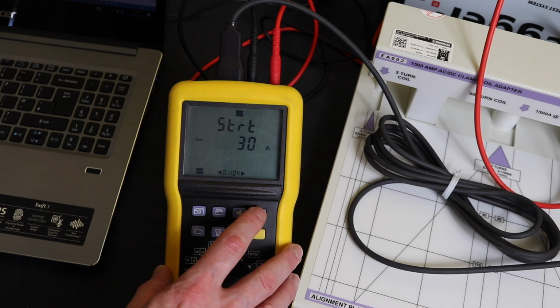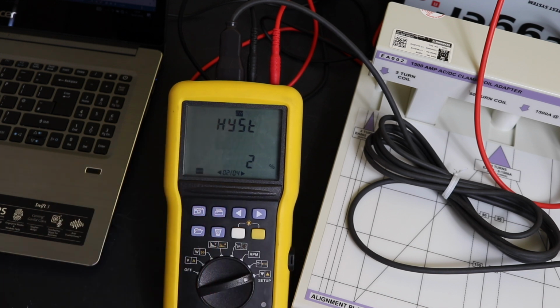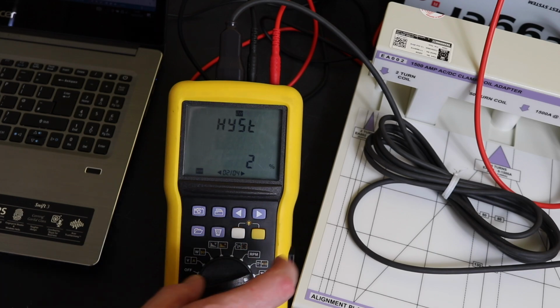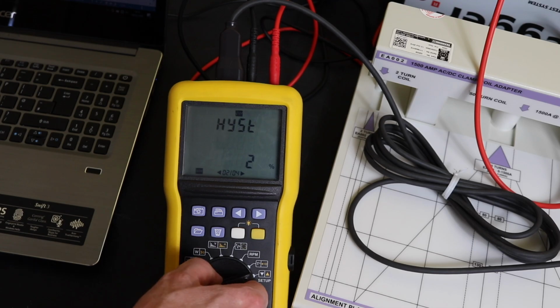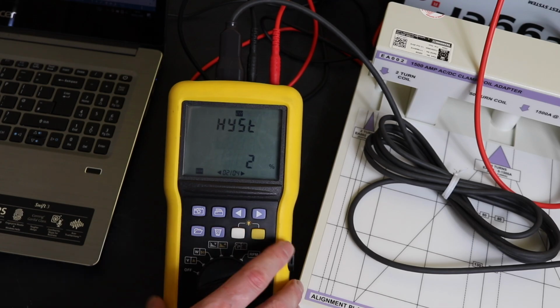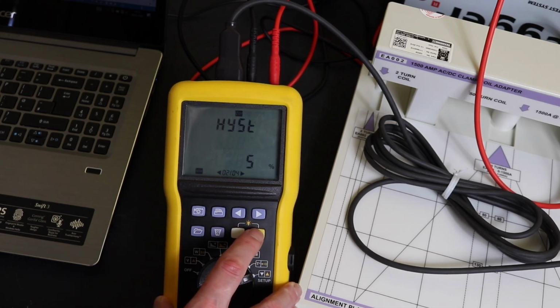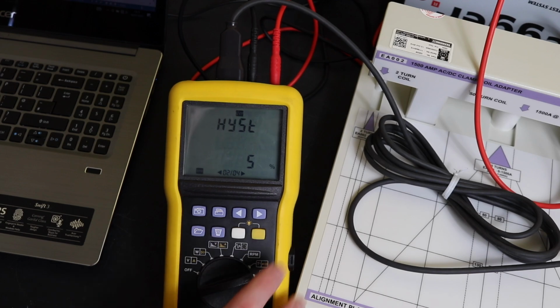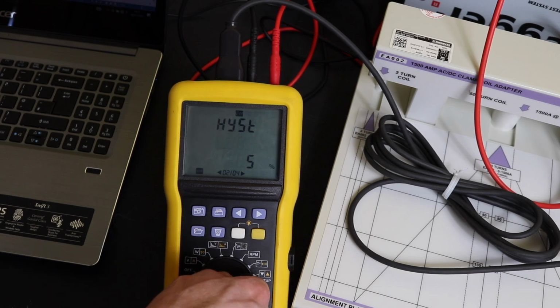I've got that set to 30 amps, and then on the next screen is our hysteresis for how it sits between the steady state current and the Inrush current. So those are the two settings that you need to set up, or you can adjust and play with whilst you're doing this instrument. I believe it's in percentage as well, yeah, so it's fixed values, 1, 2, 5 or 10%. Leave that on 5, see what happens.